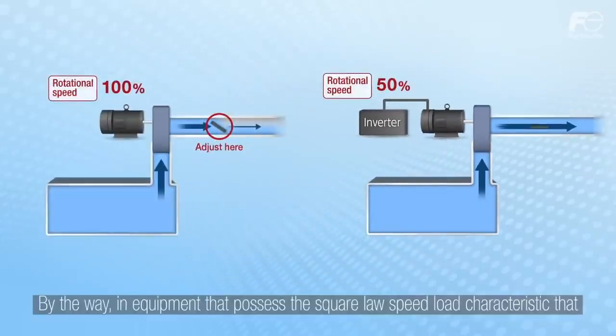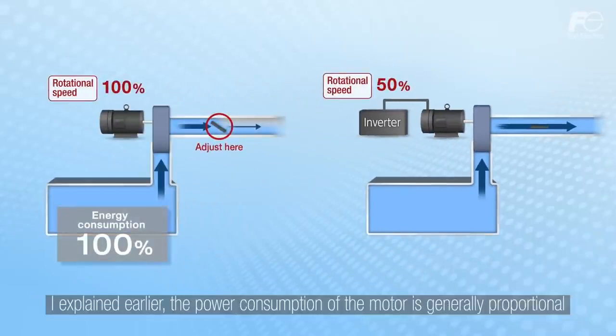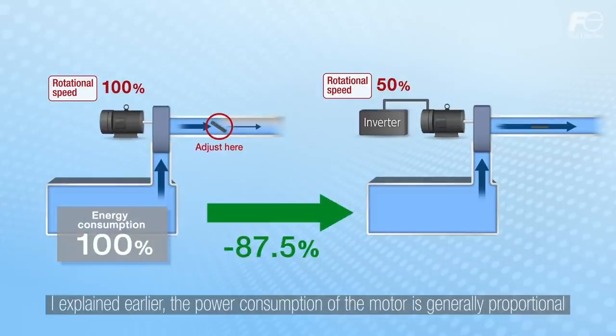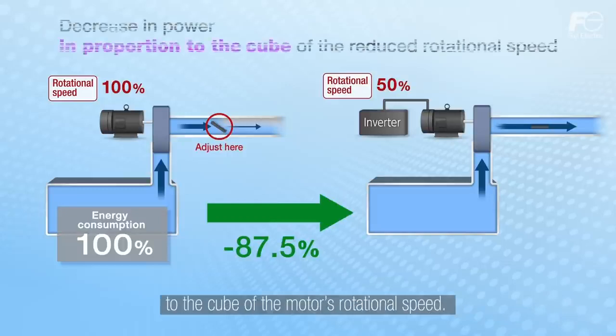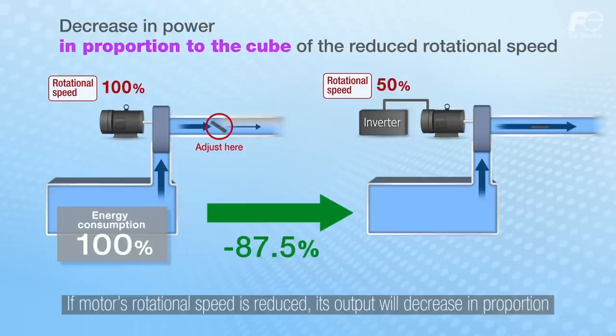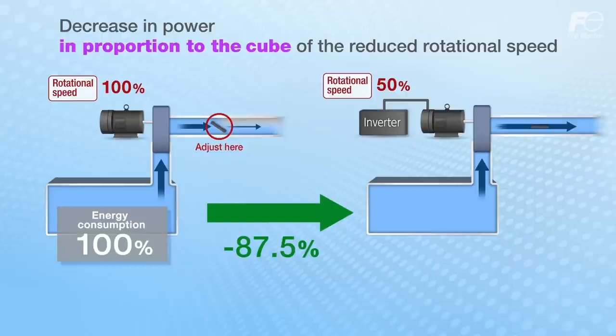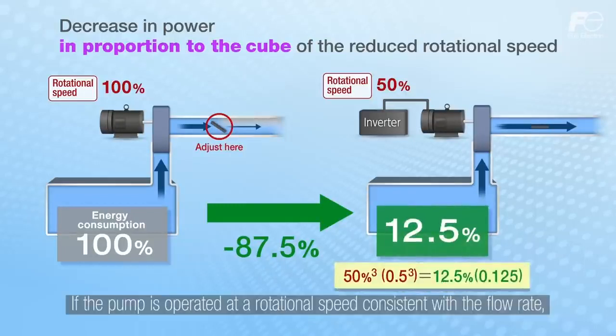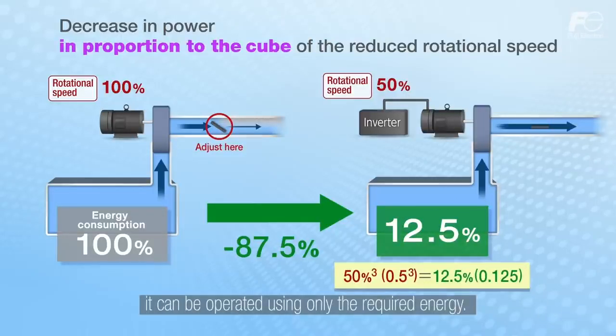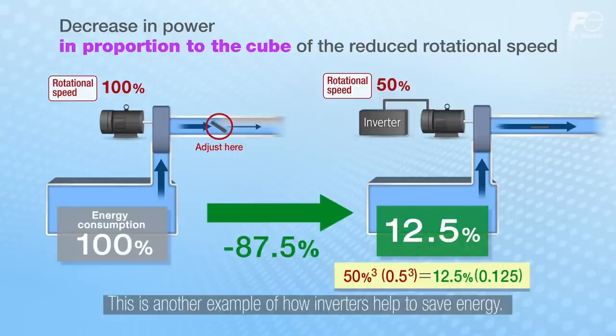By the way, in equipment that possesses the square law speed load characteristic that I explained earlier, the power consumption of the motor is generally proportional to the cube of the motor's rotational speed. If the motor's rotational speed is reduced, its output will decrease in proportion to the cube of the speed. If the pump is operated at a rotational speed consistent with the flow rate, it can be operated using only the required energy. This is another example of how inverters help to save energy.